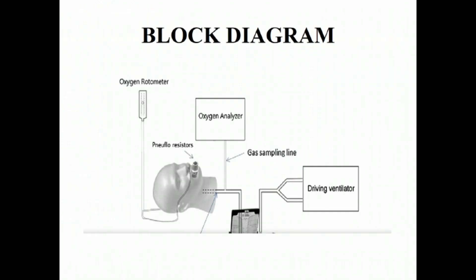In ventilators, there is a need for measuring oxygen purity of the medical gas that is supplied to the patients. It is often provided with oxygen analyzers for measuring oxygen purity to prevent the conditions of hypoxemia. Here, we have shown the representation of ventilators connected to the oxygen analyzer for measuring oxygen purity that is being supplied to the patients.